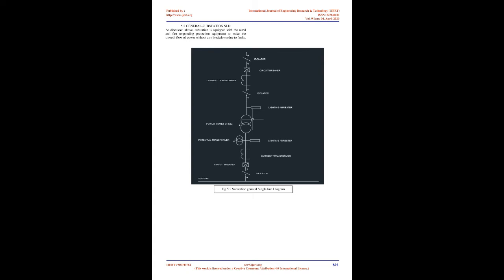The DC power from solar generation is inverted to AC power, which is collected and passed to the inverter duty transformer. With the help of LT cable, power is transferred from the inverter to the IDT, where the power is stepped up by the transformer. After step up, using HT cable, it is passed to the 33 kV switchgear.